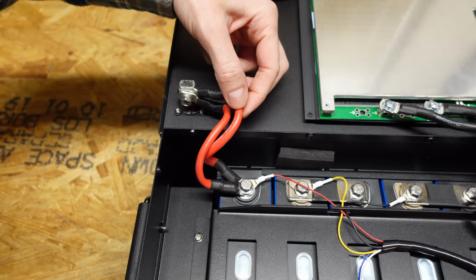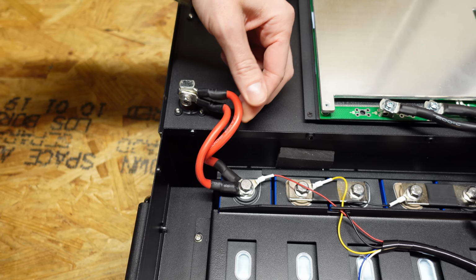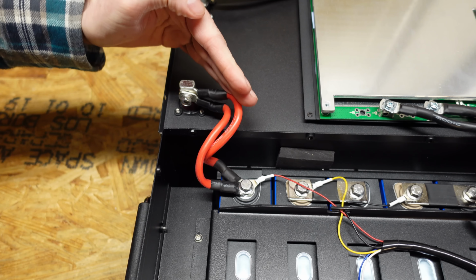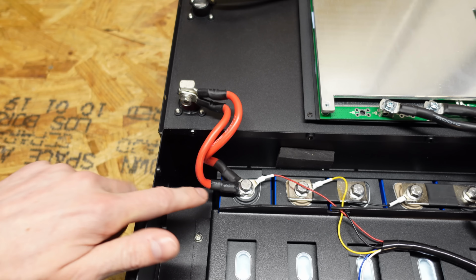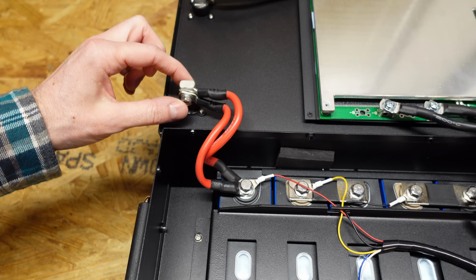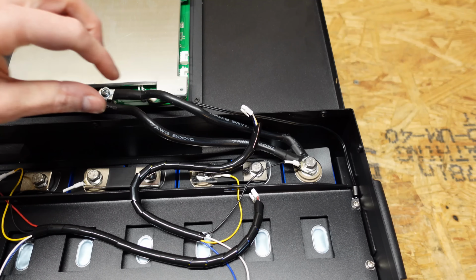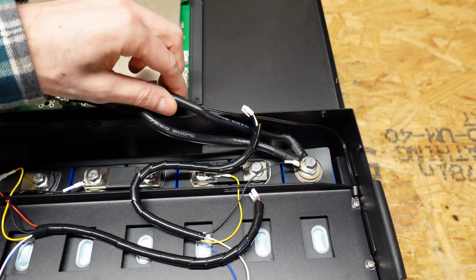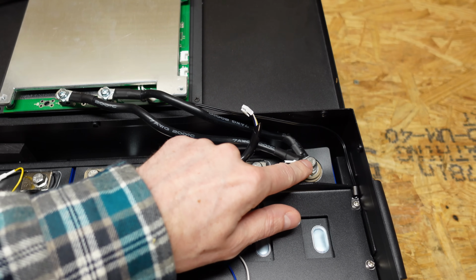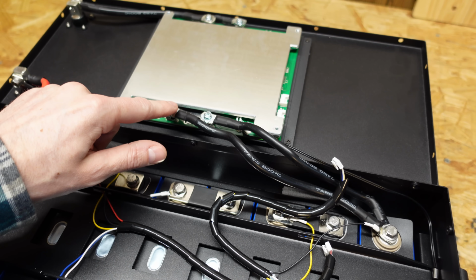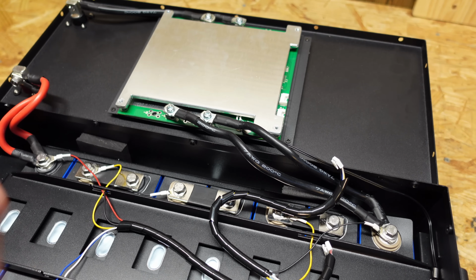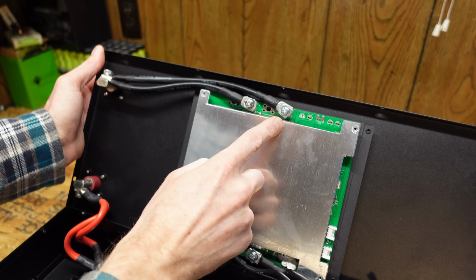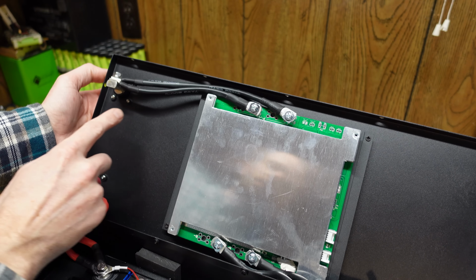The main positive connection is a pair of 7 gauge silicone insulated wires, 200 degree Celsius insulation rating. They're bolted down to the top of the cell and then bolted down to the lug at the top. The main negative is done the same way: a pair of 7 gauge wires bolted to the cell, then going up to 2 separate screw pads on the BMS.